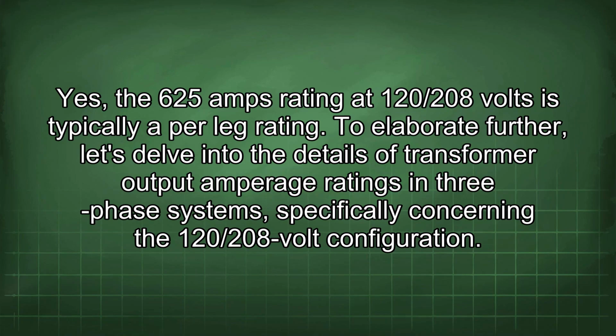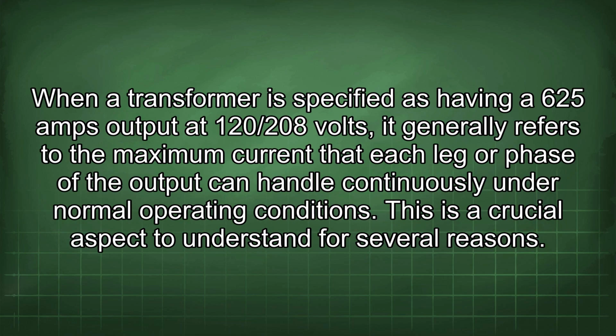Yes, the 625 amps rating at 120/208 volts is typically a per leg rating. To elaborate further, let's delve into the details of transformer output amperage ratings in three-phase systems, specifically concerning the 120/208 volt configuration. When a transformer is specified as having a 625 amps output at 120/208 volts, it generally refers to the maximum current that each leg or phase of the output can handle continuously under normal operating conditions.